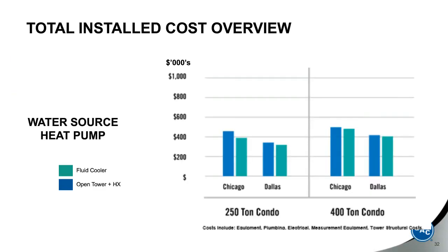Now let's look at a system that needs a closed loop, which is a water source heat pump. Again, the y-axis is the installed cost for the system. The fluid cooler, again, is shown in green, and the blue is the open tower heat exchanger. For the 250-ton condo case, the fluid cooler offered lower installed costs in both Chicago and Dallas. For the 400-ton case, the costs were closer together, but still the fluid cooler was slightly better in both Chicago and Dallas.